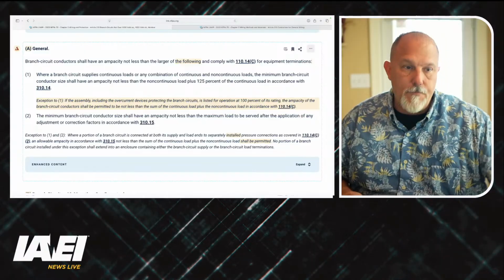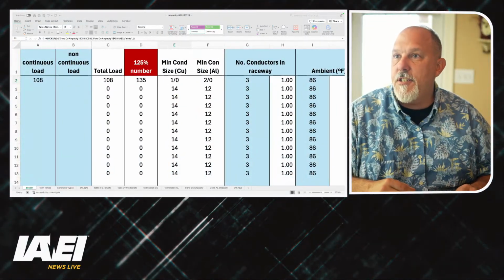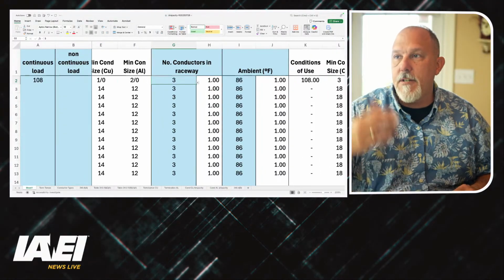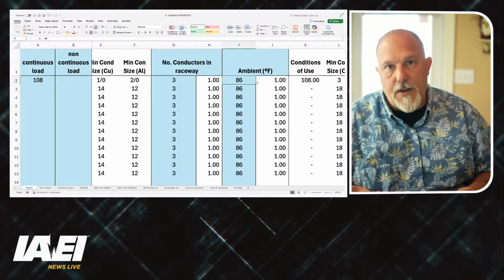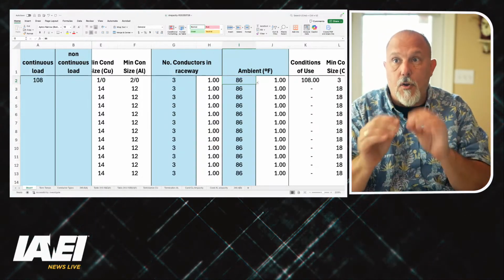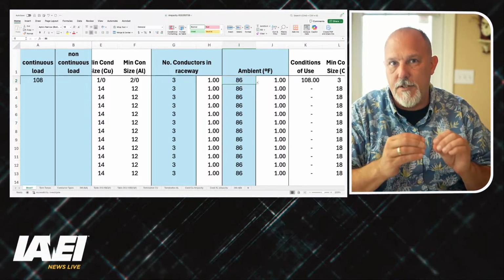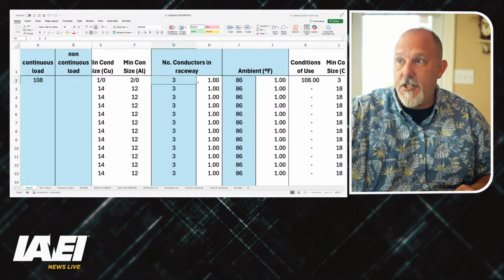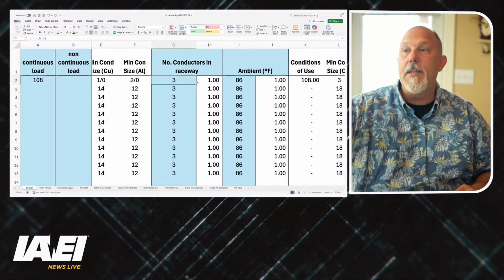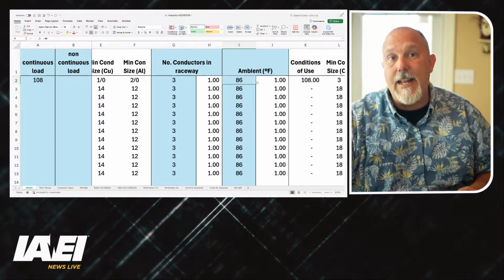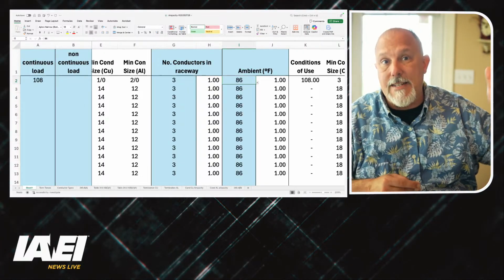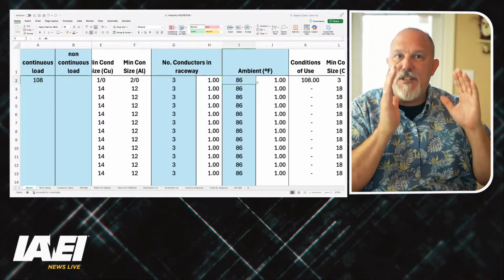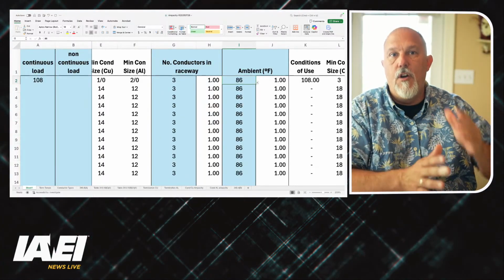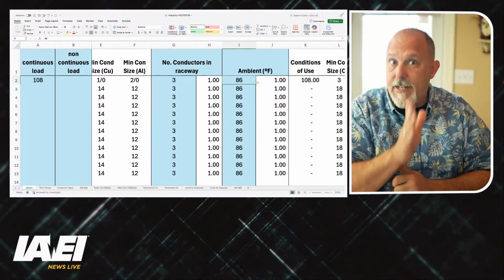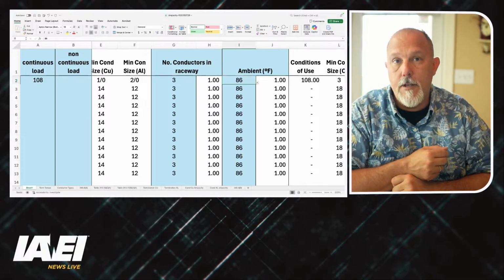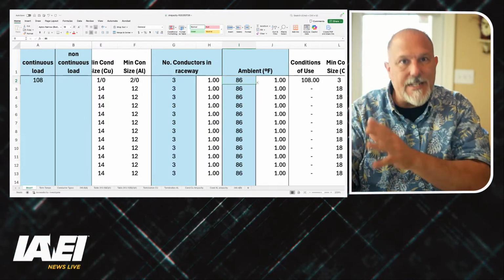So for our example, my conditions of use are going to be 3 conductors in a raceway and 86 degrees Fahrenheit. Now we can change these and see what happens, but let's start with something simple first. All right? And these conditions of use of 3 current carrying conductors in a raceway and 86 degrees Fahrenheit ambient aligns with table 310.16 conditions of use. So the ampacities found in that table for the insulation rating, which we're going to use 90 degrees C insulation, are accurate for this application.